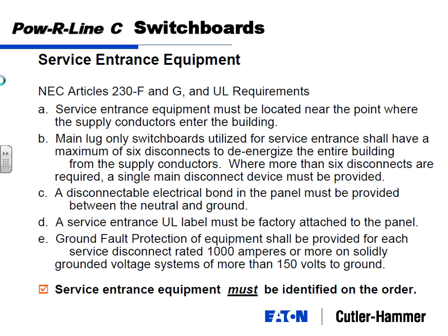I mentioned the service entrance label must be factory attached to the panel. If this comes up, you ship a switchboard or a panelboard out to the field with no service entrance label, the inspector fails it, and how do you get a service entrance label on there? It's not allowed to be done. You can't walk out there with a sticker and throw it on. It has to be done in the plant. Now, there's been push and shove where there are ways you can have the plant guy or some authorized worker come out, meet the UL guy out there, and UL guys are about $5,000 for a 3-hour visit or something like that, and reconstruct it in his witness.